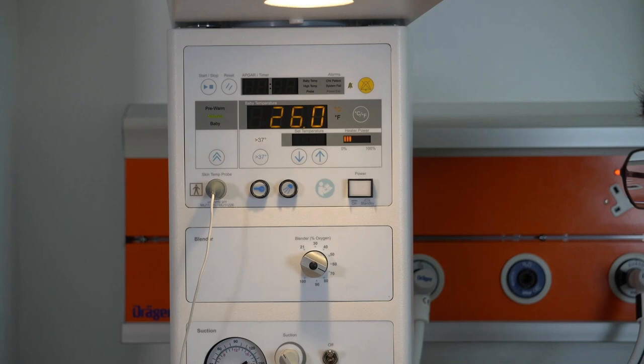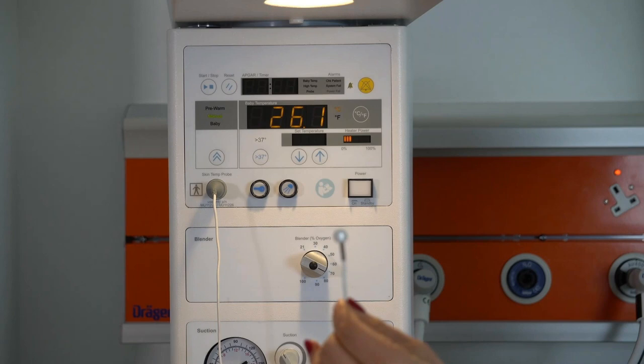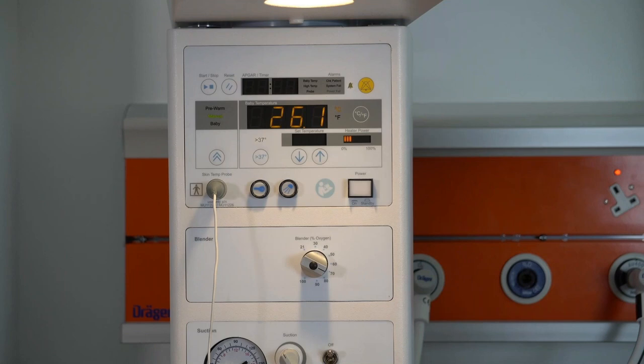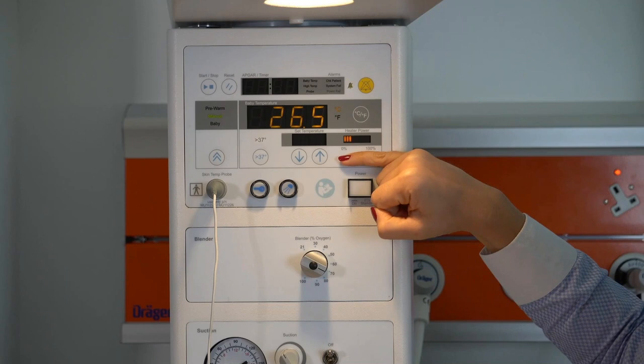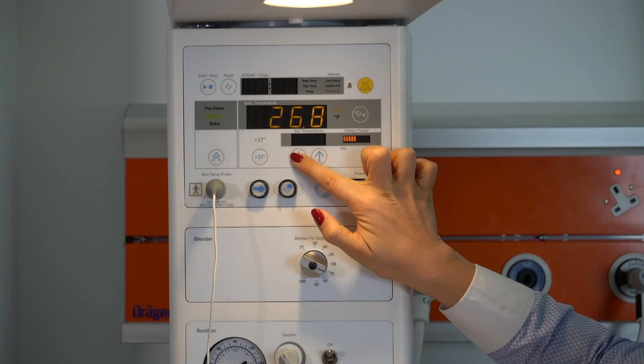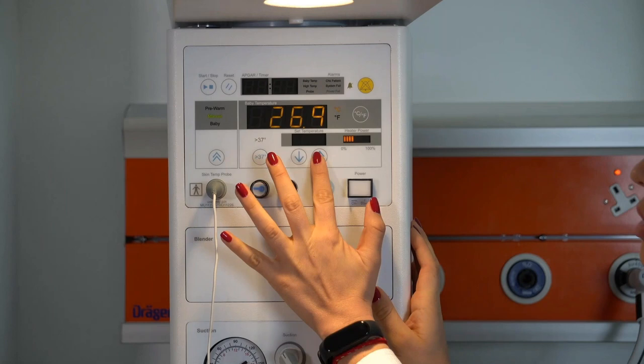So once we switch into the manual mode, first of all, by having the temperature sensor, it's a reusable temperature sensor, we are able to monitor the baby temperature. And we are able to control manually the setting of the heater output.